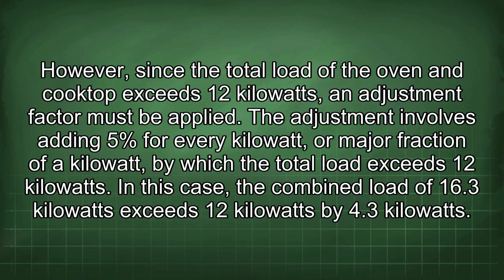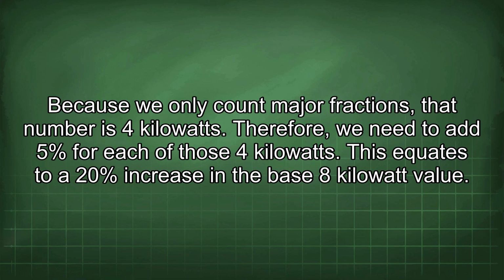However, since the total load of the oven and cooktop exceeds 12 kilowatts, an adjustment factor must be applied. The adjustment involves adding 5% for every kilowatt, or major fraction of a kilowatt, by which the total load exceeds 12 kilowatts. In this case, the combined load of 16.3 kilowatts exceeds 12 kilowatts by 4.3 kilowatts. Because we only count major fractions, that number is 4 kilowatts. Therefore, we need to add 5% for each of those 4 kilowatts. This equates to a 20% increase in the base 8 kilowatt value.